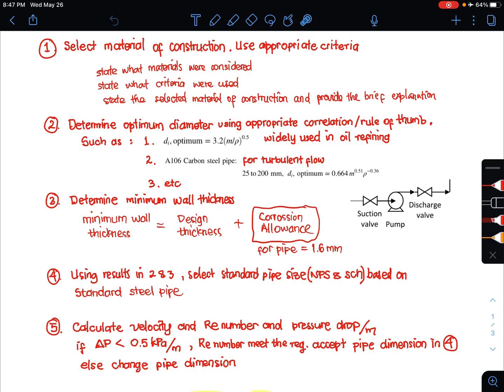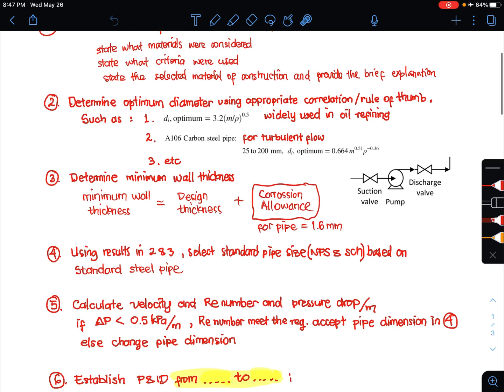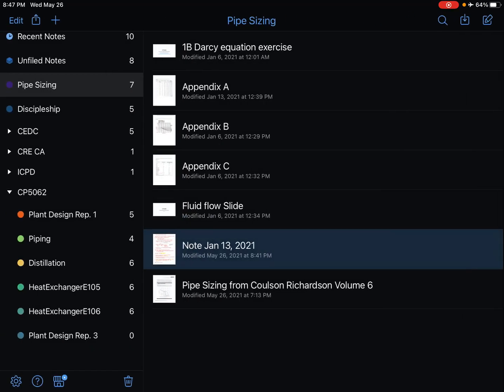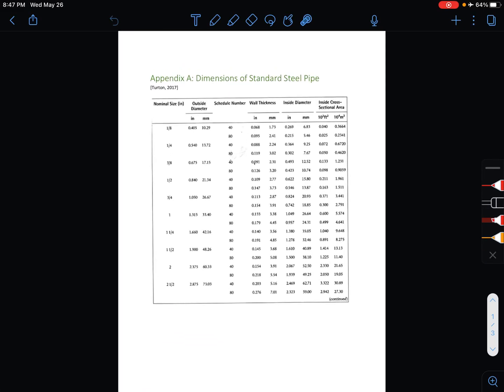Step number 4: using the results from steps 2 and 3, you need to select the standard pipe size — the nominal pipe size and schedule number — based on the standard steel pipe table. In CP5062, the standard steel pipe table can be found in Appendix A.